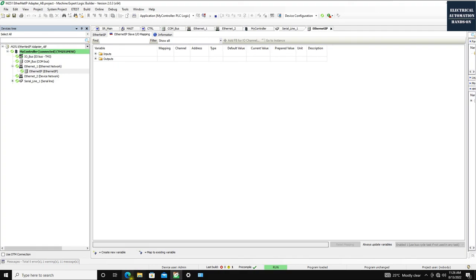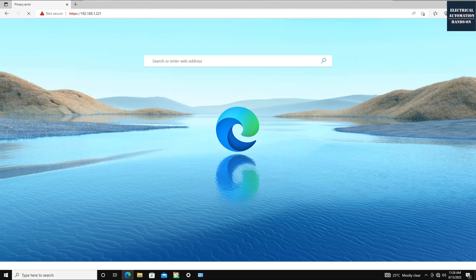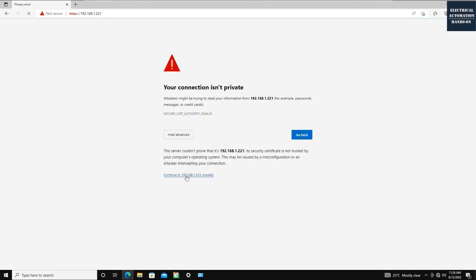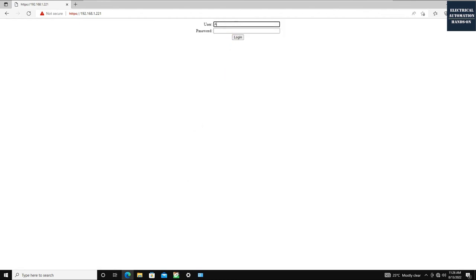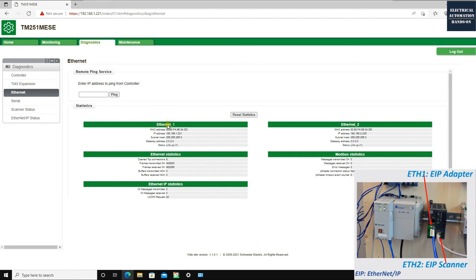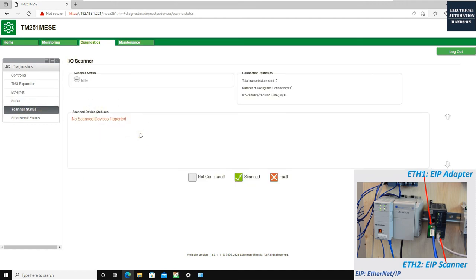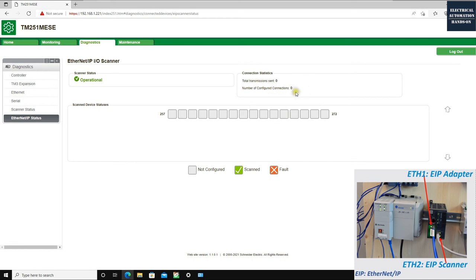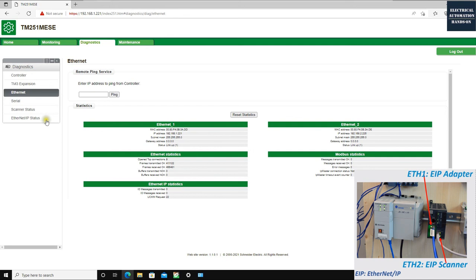Before going to the Allen-Bradley side, let's browse the controller via IE browser at 192.168.1.221. After logging into the web page with the controller credentials, go to Diagnostics and then Ethernet. We're using port 1 (IP 1.221). The 'Scanner Status' and 'EtherNet/IP Status' shown here actually represent port 2 when it runs as a scanner. For port 1 running as an adapter, there's no page to show whether the scanner has been found.